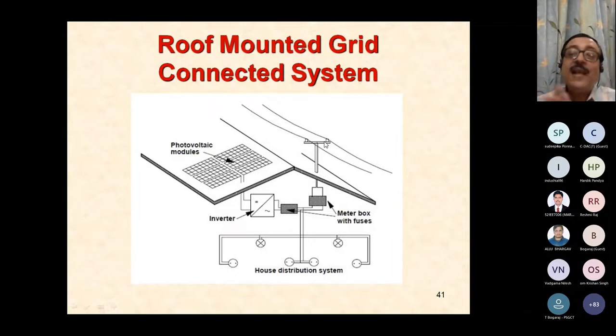Now, still there are more catches. Yes, if I have a big academic institution or an industry or a factory where I install a solar panel like this to save on my electricity bills, and yet I do not have a two-way metering, in such cases there is one more word of caution. On holidays, you have to be careful, because on a holiday, the panel will generate electricity, but there will be hardly any consumption because on the holiday, everything is shut off. So it will try to send power back into the grid, and you will have a positive reading when you come back the next working day. So your billing has increased. So on holidays, you have to ensure the disconnection of this power from either this side or this side, so that power does not flow backwards.